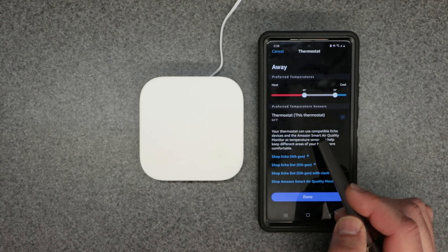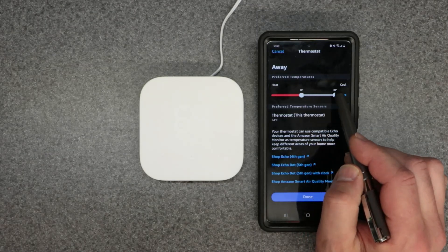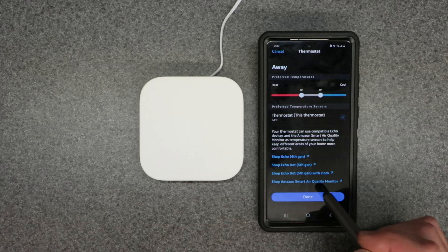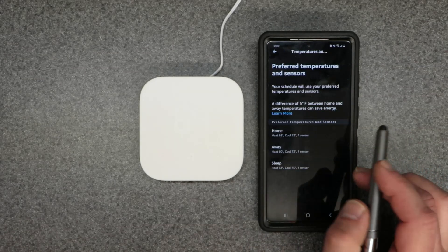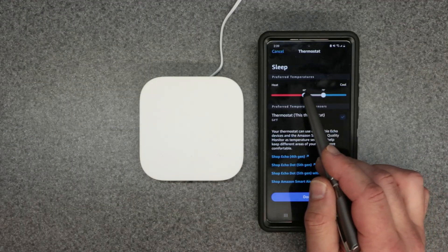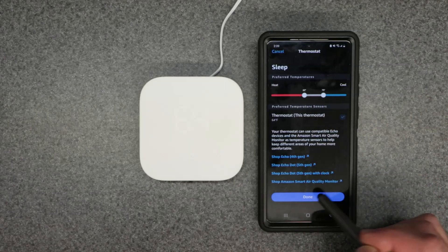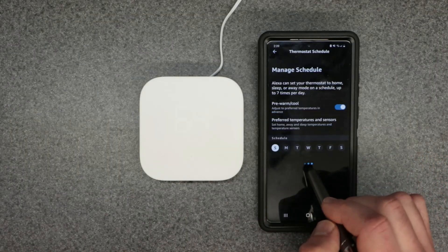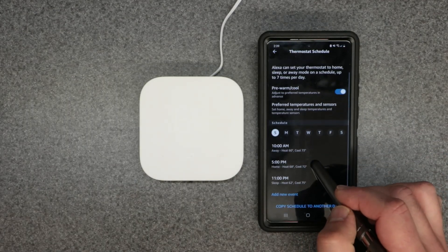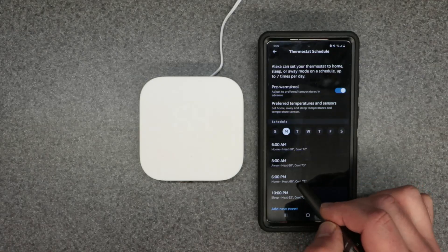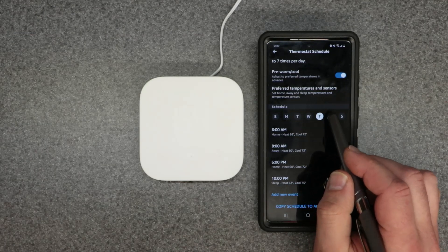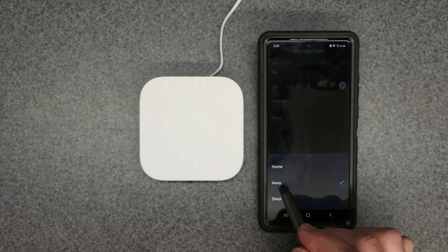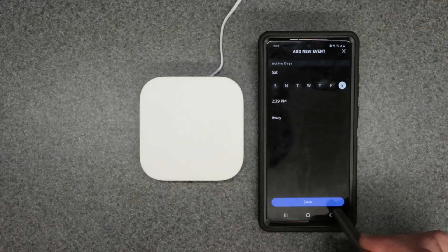Then set the Away period — for example, 60 for heating and 74 for cooling. You get the idea: adjust each time block to your liking. For Sleep, adjust the set points for that period and hit Done. That sets your temperature set points. On the Manage Schedule page you can add events for different days, selecting Home, Away, or Sleep, and then hit Save.